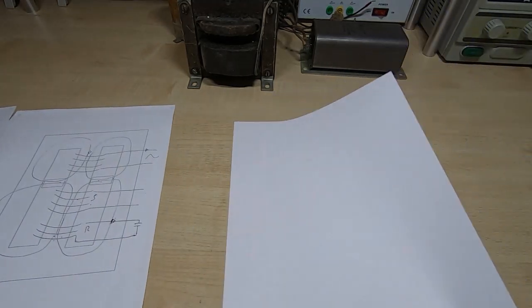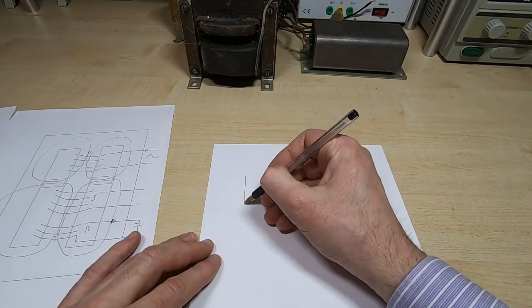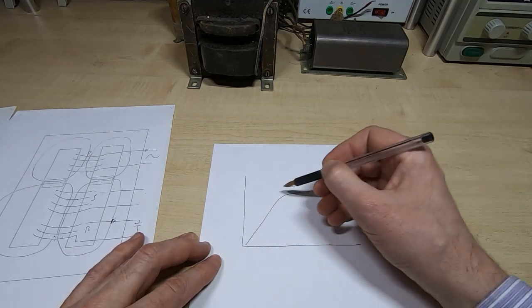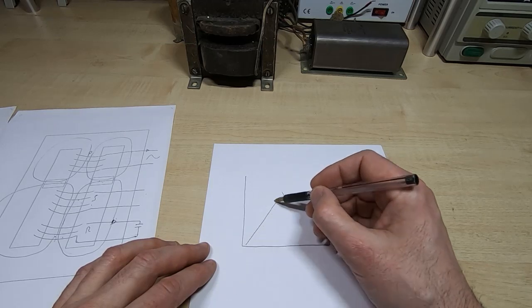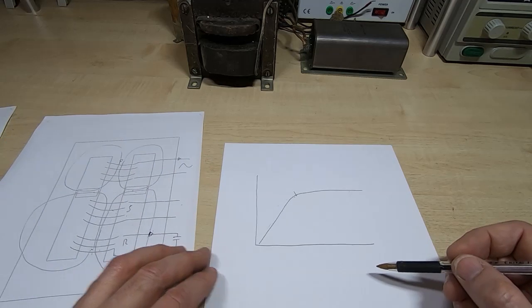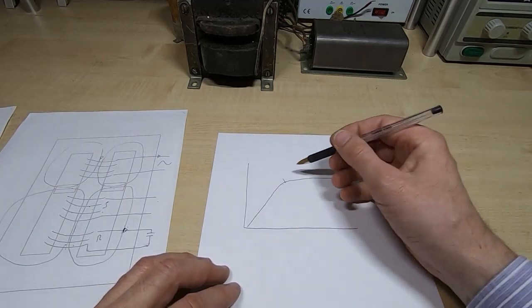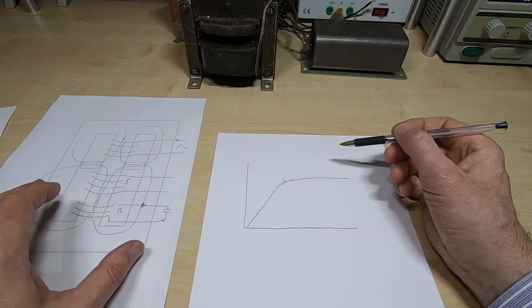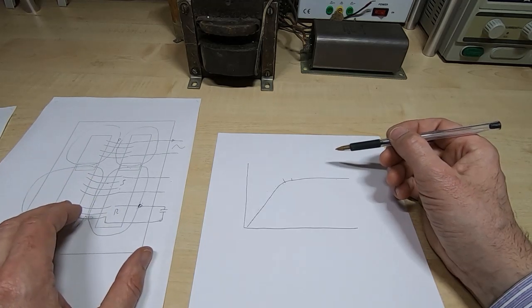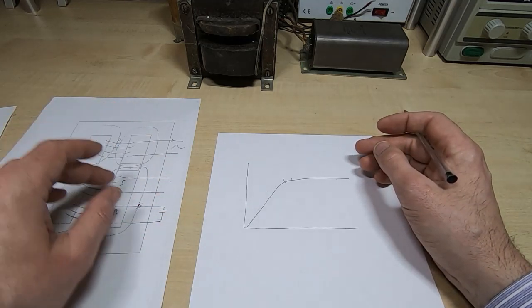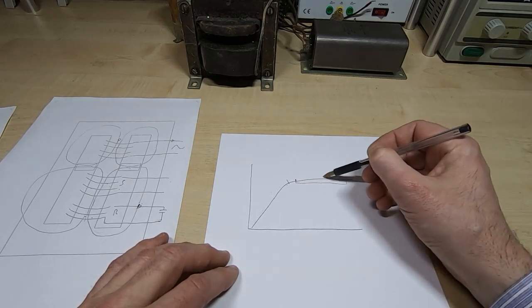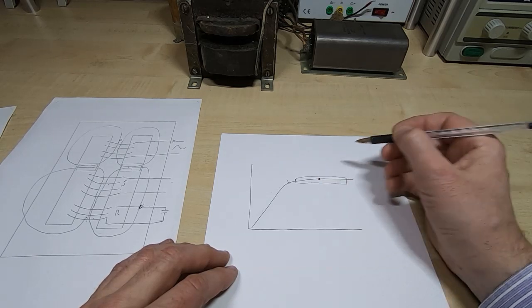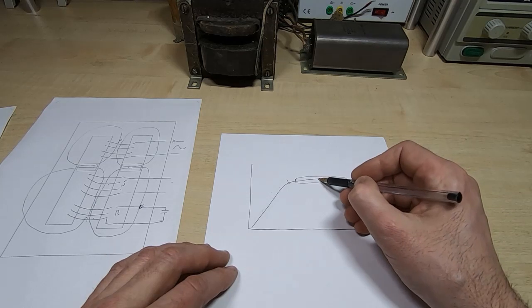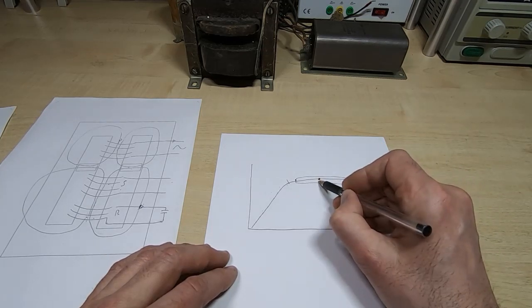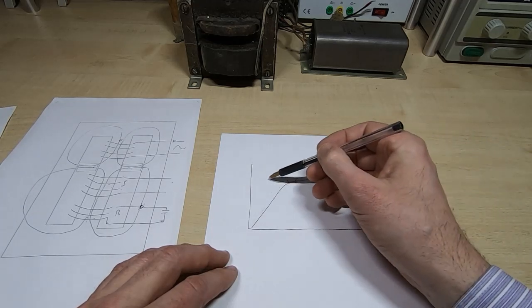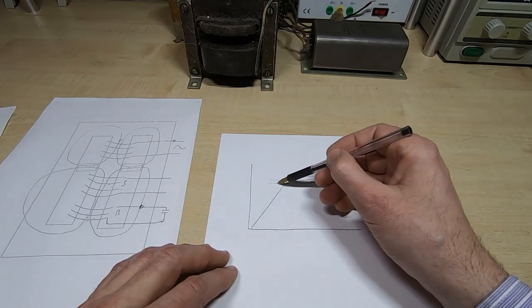So the next question is, why do we want the secondary to operate in the saturated region of the flux curve? If I redraw the flux curve, we have the knee here, and bear in mind the primary is always operating in this linear zone. We don't want the primary to be driven up into the saturated zone, which is why we have the shunts in the core. But the secondary, because of the capacitive current flowing in the secondary resonant winding, is driven into saturation, and as I say, it's isolated from the primary flux by the shunts. Because the secondary is operating in this part of the curve, let's assume that at any instant it is here. If for any reason the load on the secondary changes in such a way that the flux within that part of the transformer moves this way, you can see it's not going to have much of an impact on the voltage. The voltage range over this part of the curve is very small.